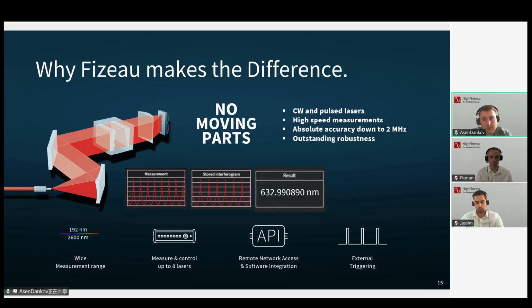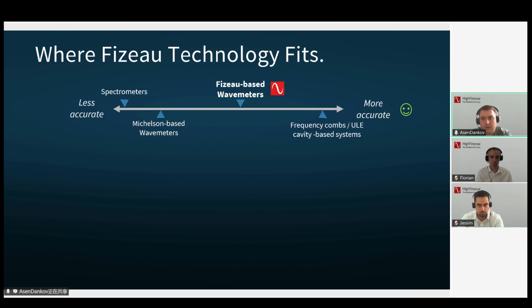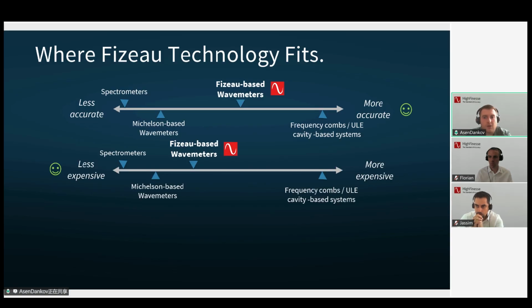With that understanding of the technology, you will now see how it's implemented across the HighFinesse product portfolio. Before we continue to the product portfolio, I'd like to put our technology into perspective. There are several ways to measure laser wavelength, and each technology has its own strengths. Let's first look at the accuracy. On the one end of the spectrum, we have spectrometers and wavelength meters based on the Michelson interferometer. These instruments have a fairly limited accuracy. At the other end of the spectrum, frequency combs and ultra-low expansion cavity systems provide extremely high accuracy. However, as we can also see, they're very expensive and complex.